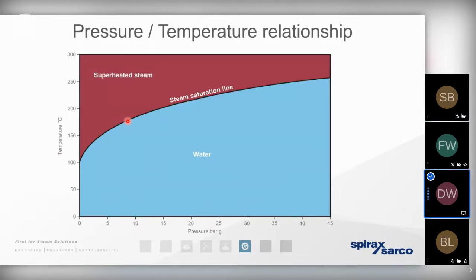But the steam saturation line also shows us something else. And this is the point at which steam gives up its heat energy and condenses. So at 10 bar gauge, the steam that gives up its heat energy either to the distribution pipework or to the heat exchanger is going to exist at 184 degrees. When it gives up its energy and condenses, there's a change of state from a gas to a liquid, but there isn't an exchange of temperature. So that means whenever condensate is exposed to the same pressure as the steam, it is going to exist at the same temperature, just as a different phase.